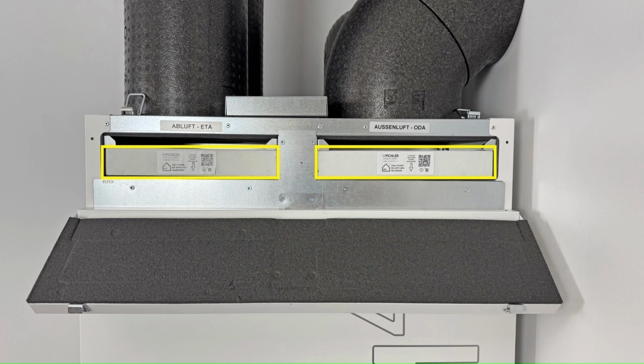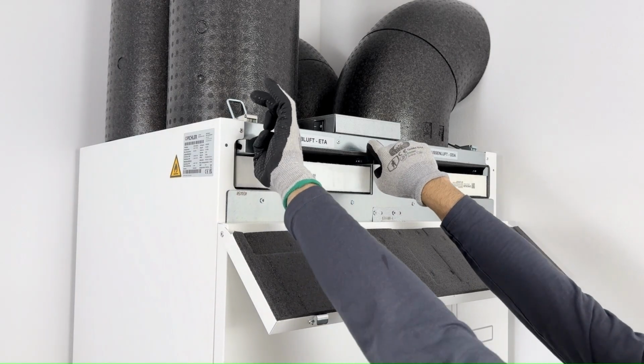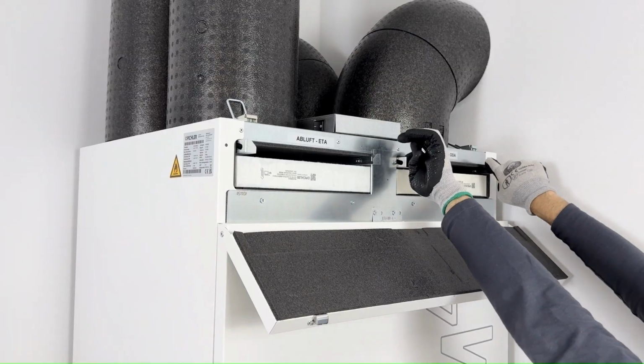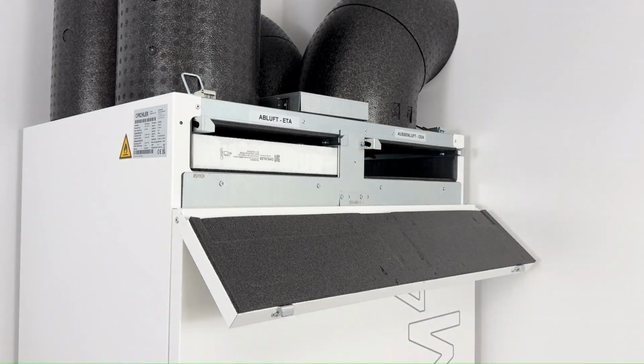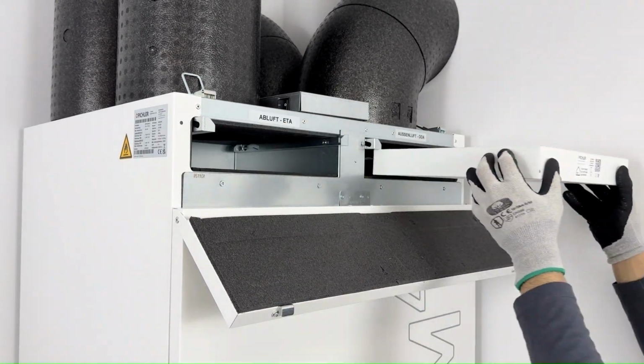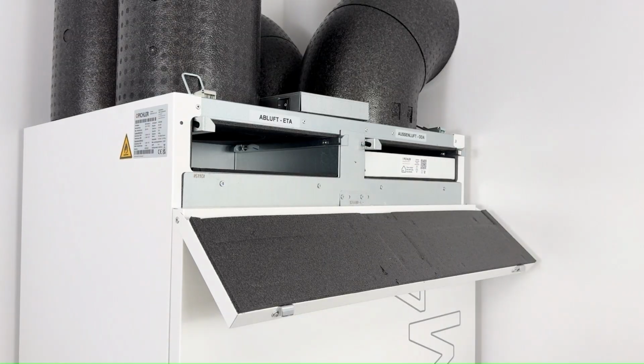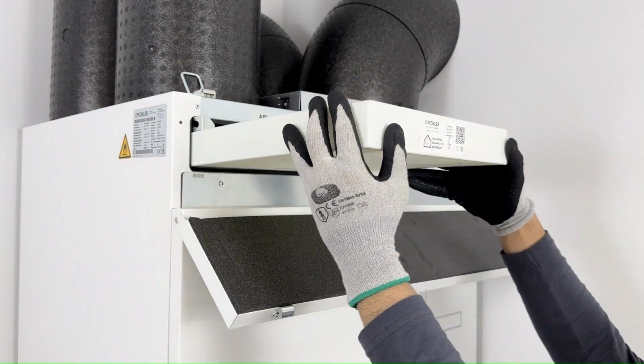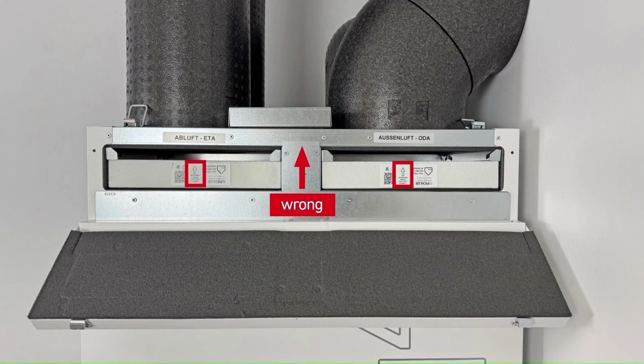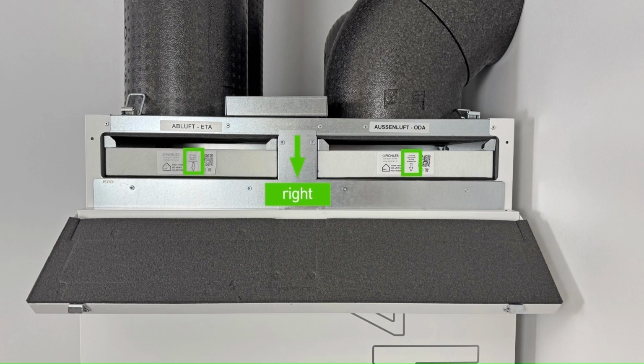The filter change is easy and can be done in only a few steps. Pull the sliders that hold the filters in position on the left and right forwards. Then remove the dirty filters. Install the new filters with care, ensuring they are properly inserted to maintain optimal performance and efficiency. Pay close attention to the direction of airflow, which is also represented on the filter itself, as shown in the accompanying image on the screen. The direction of the airflow should be downwards.